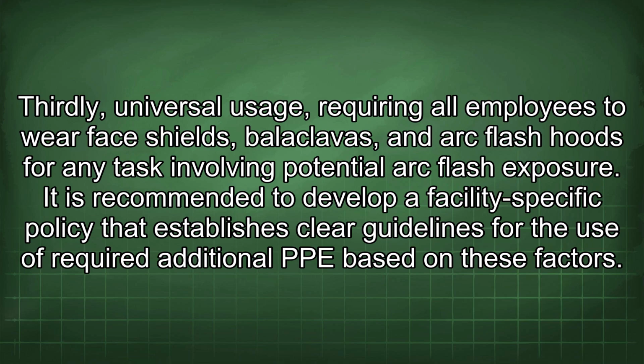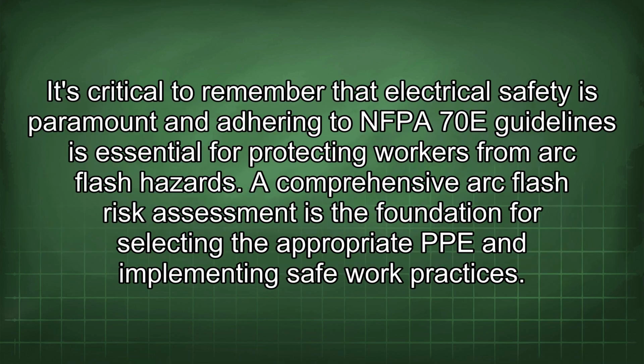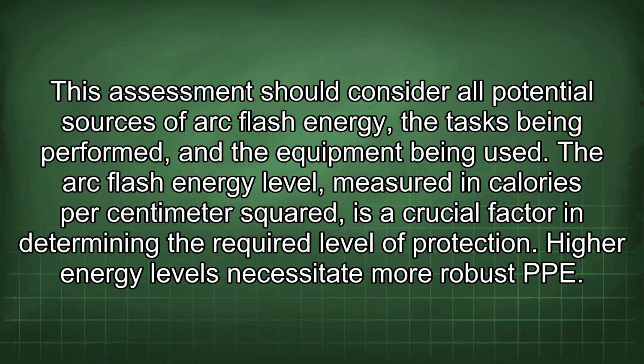It is recommended to develop a facility-specific policy that establishes clear guidelines for the use of required additional PPE based on these factors. It is critical to remember that electrical safety is paramount, and adhering to NFPA 70E guidelines is essential for protecting workers from arc flash hazards. A comprehensive arc flash risk assessment is the foundation for selecting the appropriate PPE and implementing safe work practices. This assessment should consider all potential sources of arc flash energy, the tasks being performed, and the equipment being used. The arc flash energy level, measured in calories per centimeter squared, is a crucial factor in determining the required level of protection. Higher energy levels necessitate more robust PPE.